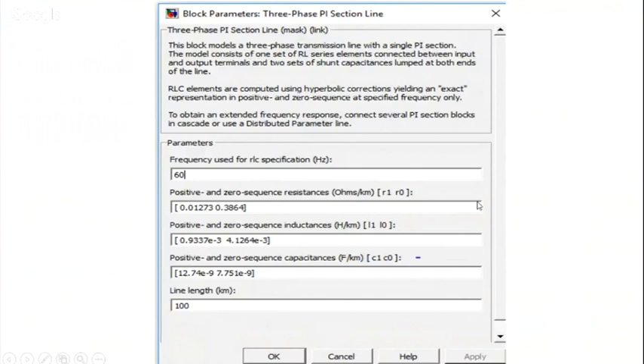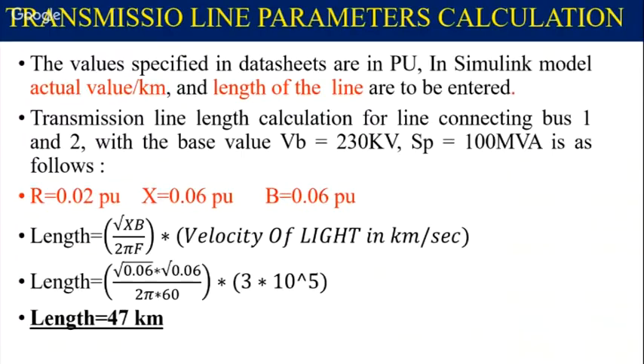So we need to calculate these values, because the datasheet we have downloaded is in per unit. That per unit should be converted to actual values, and the values per kilometer should be entered. As you know, for per unit calculation there should be a base value for the voltage and a base MVA. So here we have selected 230 kilovolts as the base voltage and 100 MVA as the base MVA. Now in our datasheet, the resistance is 0.02, X is 0.06 pu and susceptance is 0.06.